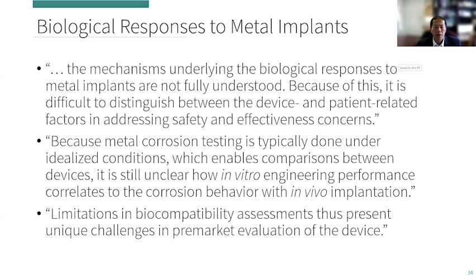However, they also recognize that there are limitations with how corrosion testing is typically performed under idealized conditions, which enables comparisons between devices, but makes it unclear how to relate the test conditions to how the device may behave in the body. But again, typically these are not done in isolation, and there are other considerations conducted to better assess that. The FDA also recognizes that even biocompatibility assessments present some limitations in evaluating device safety and effectiveness.